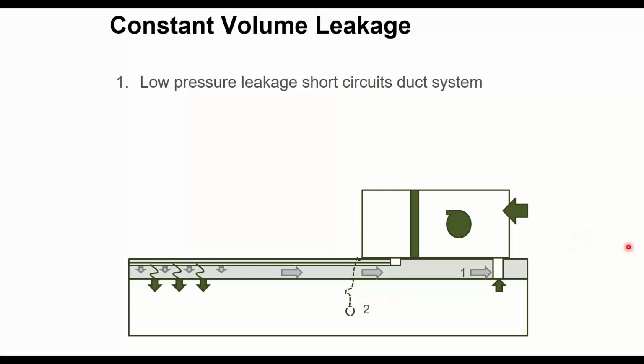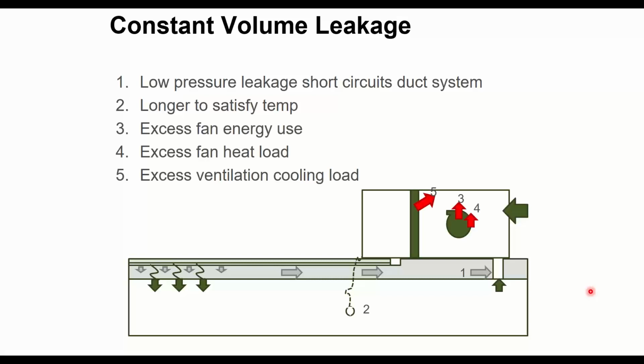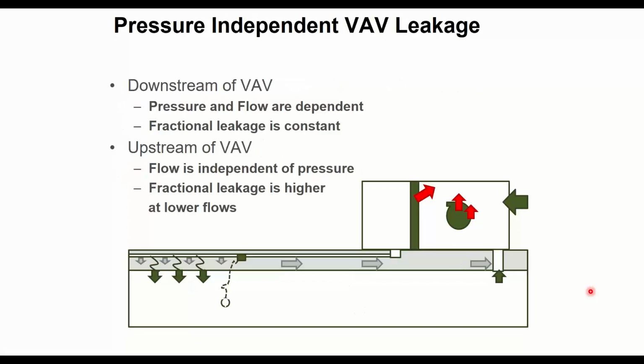Low pressure leakage, short circuits a duct system. This is constant volume systems. We'll do VAV in a second. It takes longer to make temperature. If I'm losing some of my air, it's not getting into the space. I have to run my system more than I wanted to run it in order to achieve the desired heating or cooling set point in the space. It requires me to run my fan more than I wanted to. It means I have more fan heat waste added into my duct system. Lots of negatives to this duct leakage.